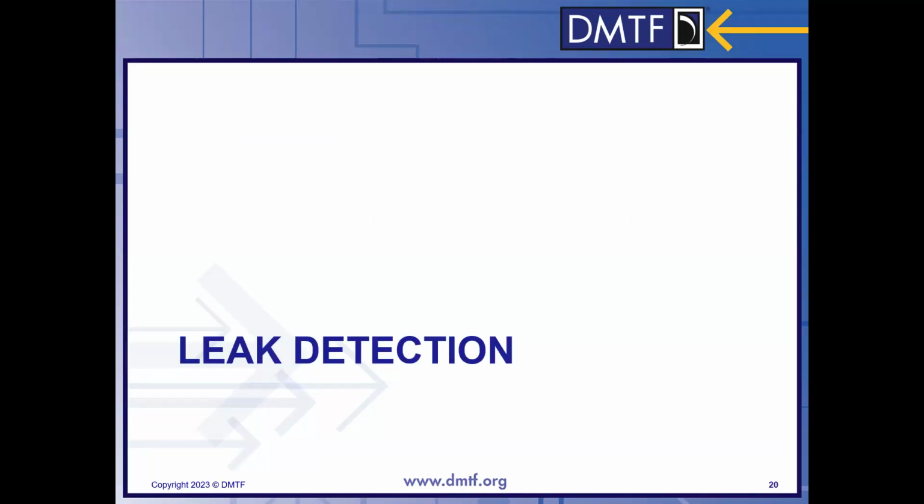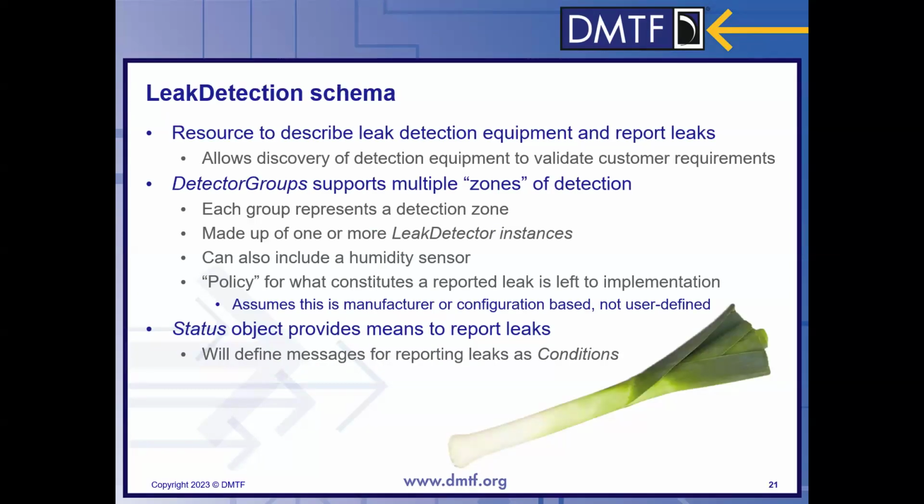This was an area that did extend the Redfish model in some other ways. We had started trying to do these discrete value types of sensors, and that just gets really bogged down into a whole area that we didn't want to get into. So we came up with what I think is a better answer, and we've explicitly defined a leak detection subsystem. Leak detection is a huge topic for all the liquid cooling folks, so we did take quite a bit of care on this topic.